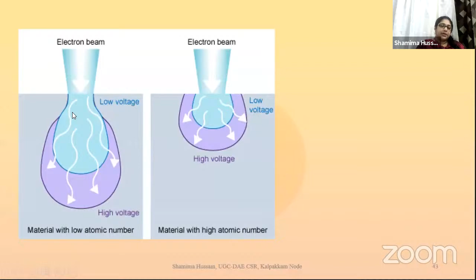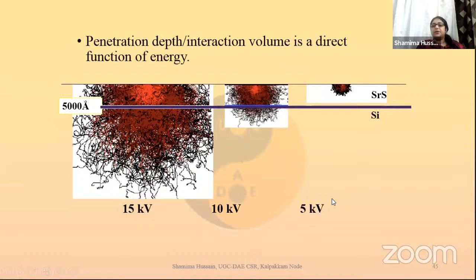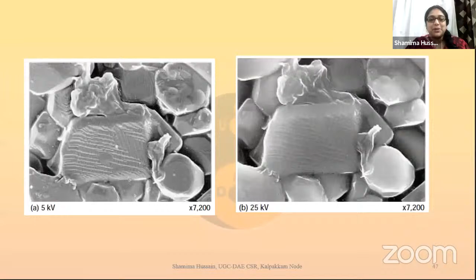Penetration depth: please see here that at 15 kV acceleration voltage the penetration volume is huge. 10 kV is small and 5 kV is even smaller, right? So if I have a higher acceleration voltage, the advantage is high resolution, but we do not always get that resolution because sometimes our samples may not be very sensitive. For this, we need some sample preparation, which we cannot discuss right now. I'm going beyond time, so if you have questions, I can take them.